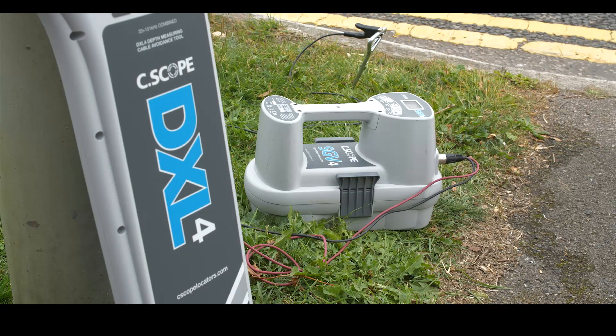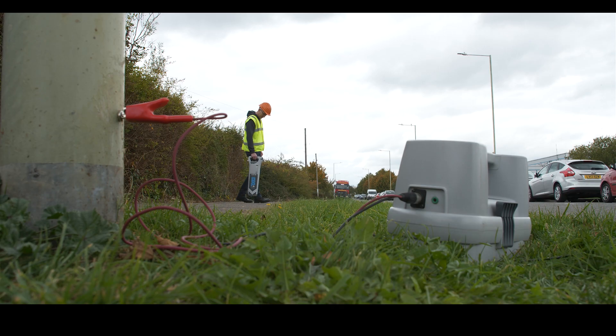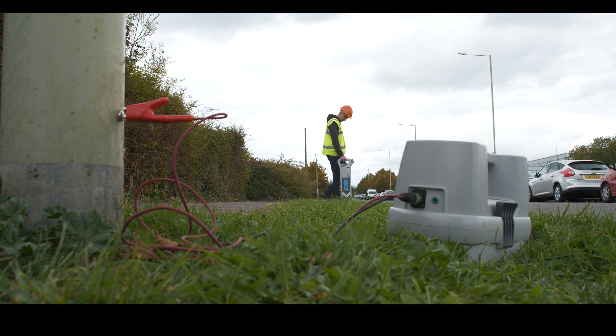One of the most effective methods of detecting the exact route of electricity cables supplying items of street furniture is to energize the cable with the signal from a C.Scope signal generator using the direct connection method of signal application.